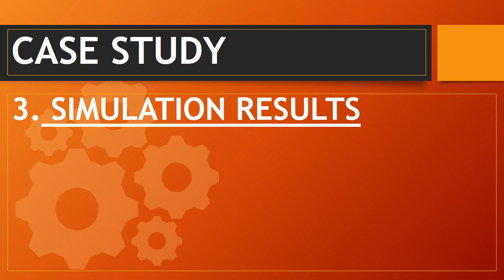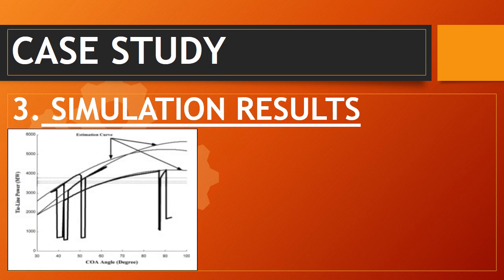Now to sum up, we assume that the Taiwan power system was armed with the PMU based SPS. Then the 729 event is simulated again. The estimated parameter results of the OMIB system using real-time phasor measurements are shown in this figure, Figure 8. The remedial action is taken after the second fault fails. The amount of remedial action is 1332 megawatts. That is, the rejection of southern generation is 1332 megawatts, and the shedding of northern load is 1332 megawatts.